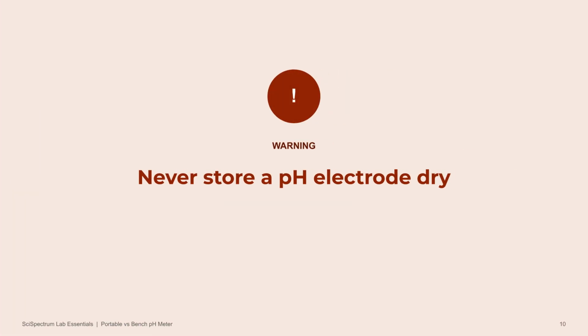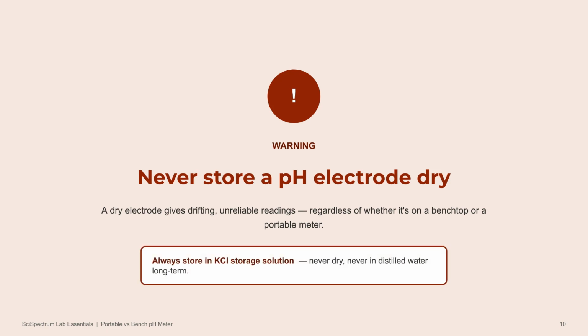And this next one is important enough that I want to call it out on its own slide. Never store a pH electrode dry. It doesn't matter whether it's sitting on a benchtop or riding around in a field kit. A dry electrode gives you drifting, unreliable readings, full stop. Always store it in KCl storage solution. Never dry, and never in distilled water long term. This one habit prevents more bad data than almost anything else on this list.